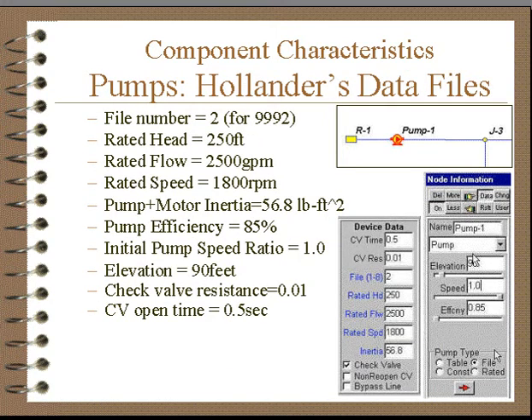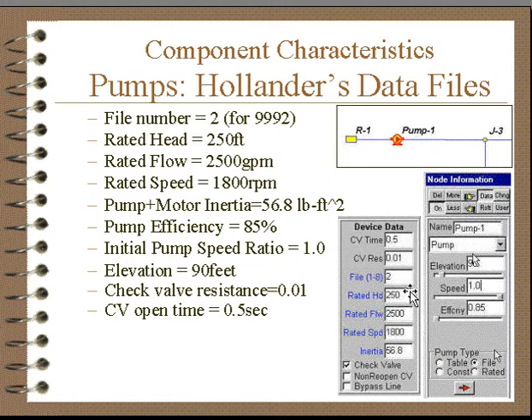A pump description which is primarily available for transient analysis is using the Hollander data files, which are the dynamic head flow characteristics. We have a total of eight files, one through eight, and we can select which file it is.